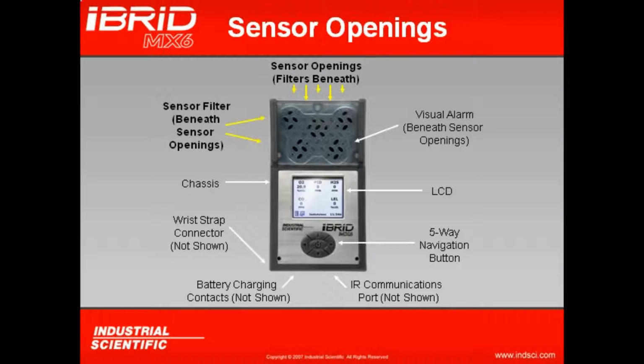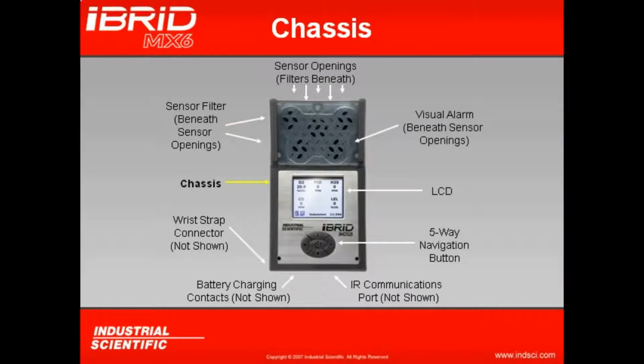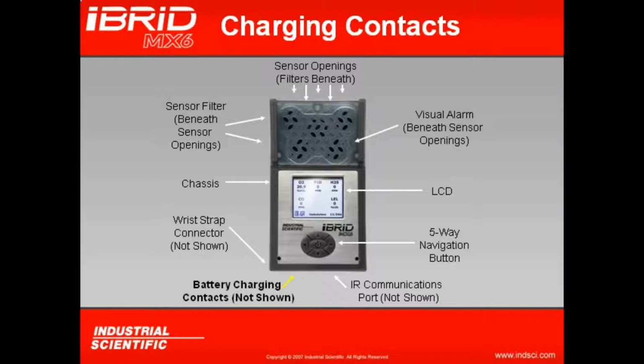If we allow any dirt or contaminants to get clogged in the inlet ports, then the sensors will not be able to see the gas. If the sensors cannot see the gas, then the instrument will not be able to detect the gas. The chassis of the instrument is a composite material with a rubber overmolding, which helps against shock or during drops. Down the corner of the instrument is where a wrist strap can be connected. At the bottom of the instrument is where your battery charging connections are located. This is for charging the optional lithium-ion battery pack.